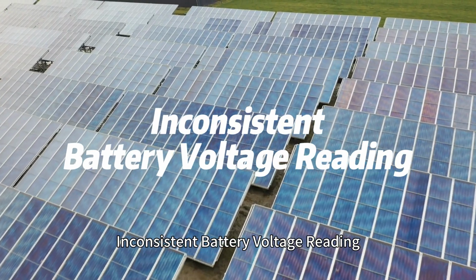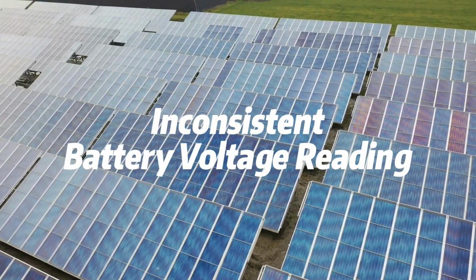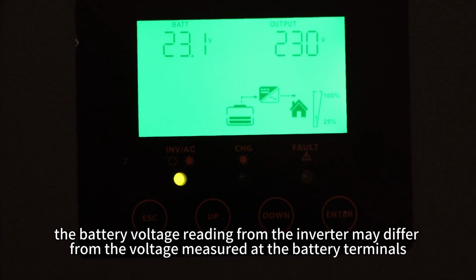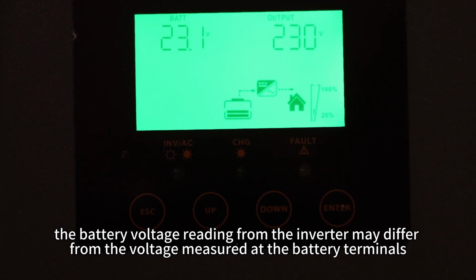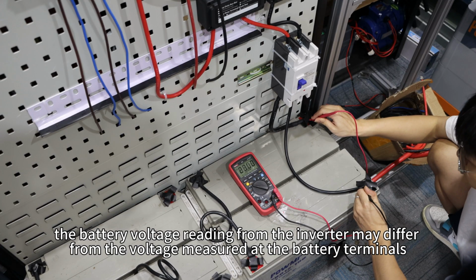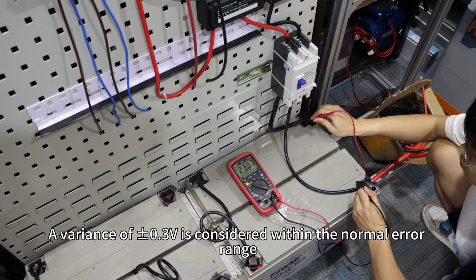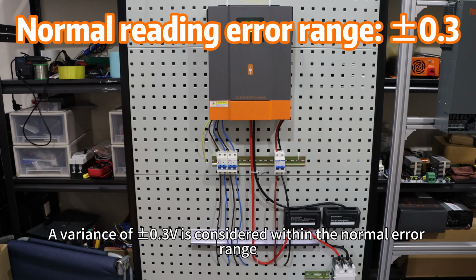Inconsistent battery voltage reading. Sometimes the battery voltage reading from the inverter may differ from the voltage measured at the battery terminals. A variance of plus or minus 0.3 volt is considered within the normal error range.